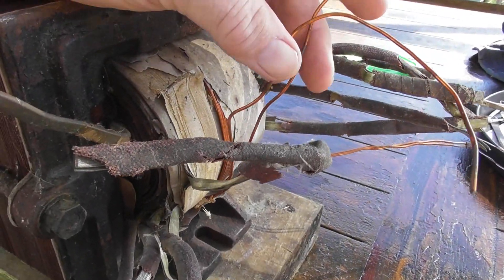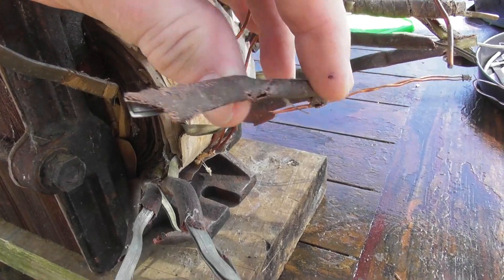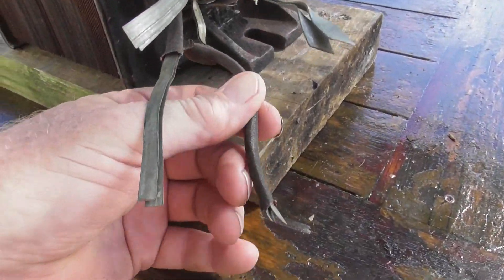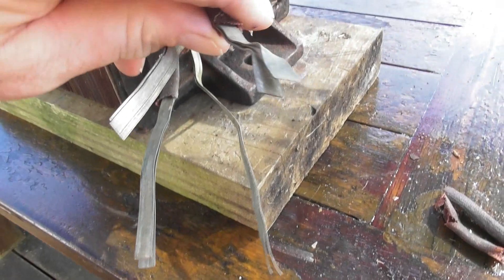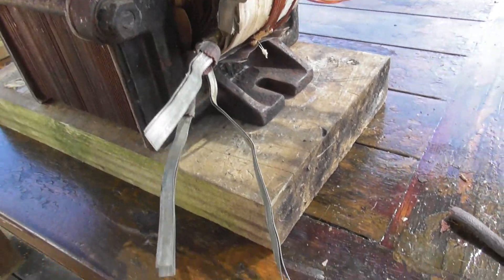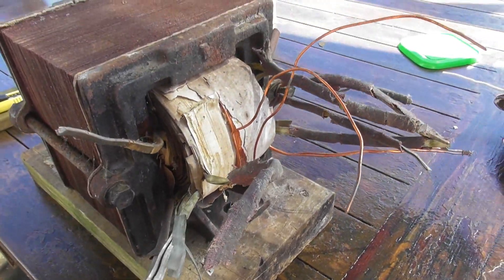I need to do some ohm measurements and see what is related to what, but I'm pretty sure they're taps. I need to put some new sleeves on this because the insulation has gone very brittle - look at this, it breaks off quite easily. You don't want that shorting out. Also need an insulation test on the device. I'll start cleaning this off a bit and advance on this video a bit later.